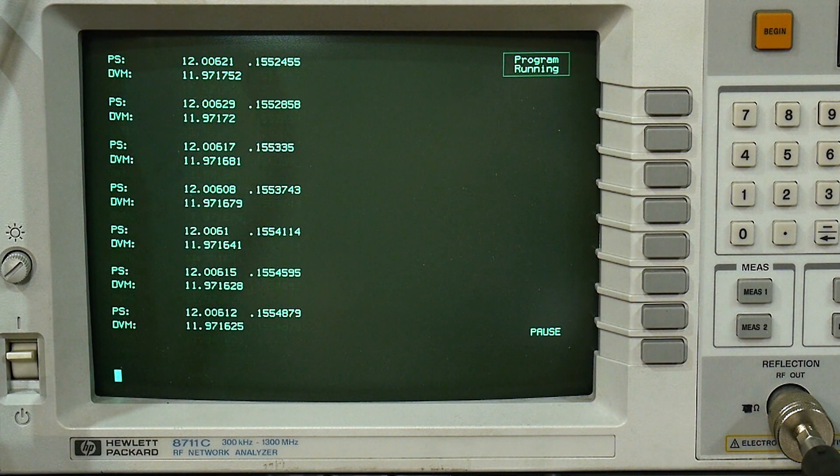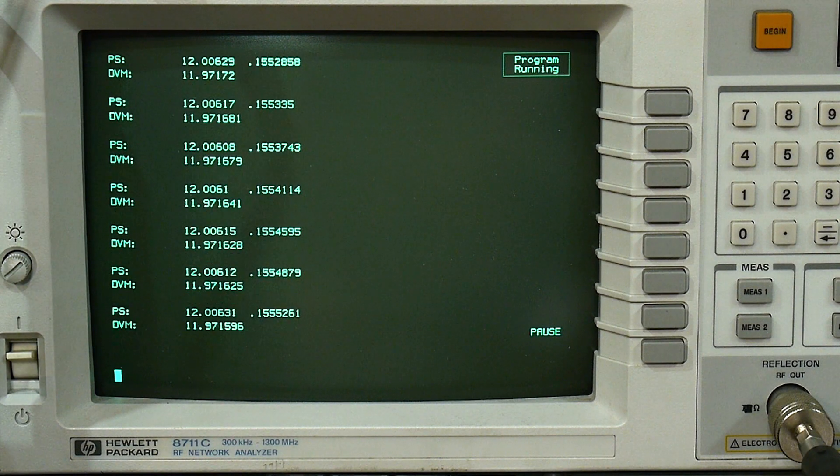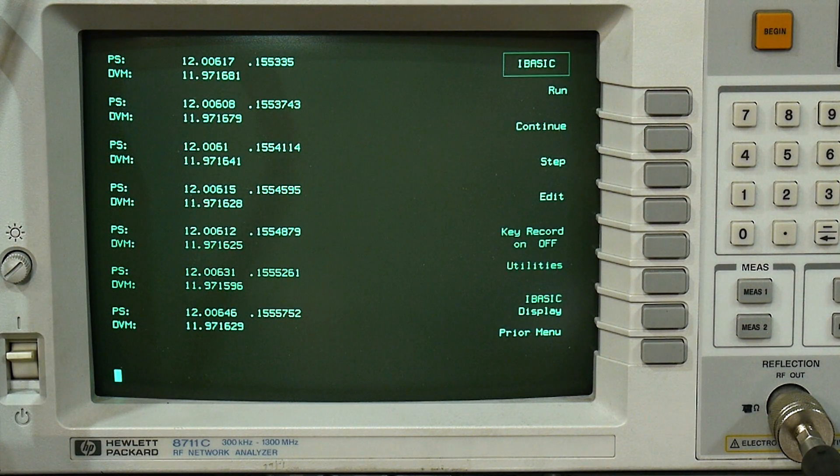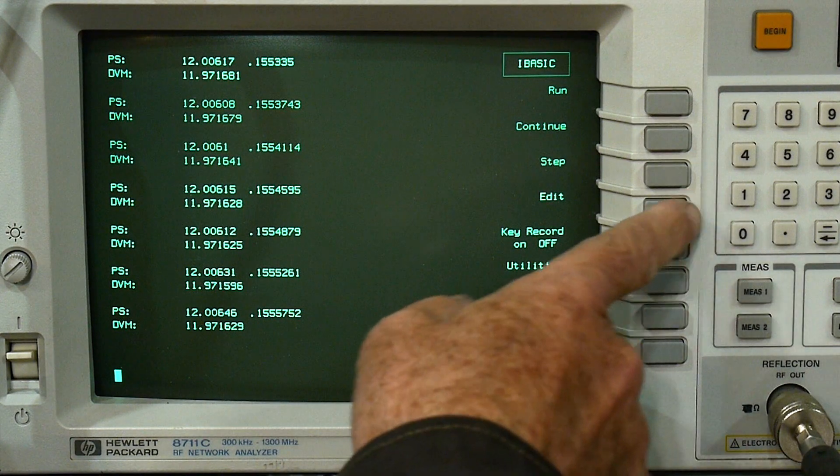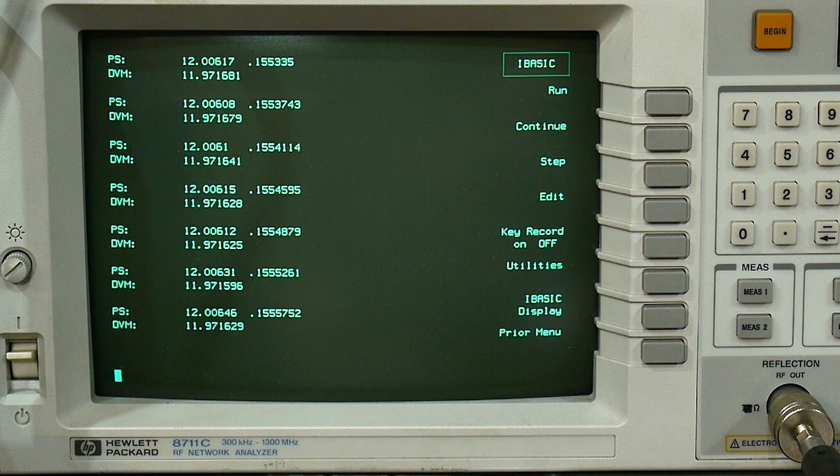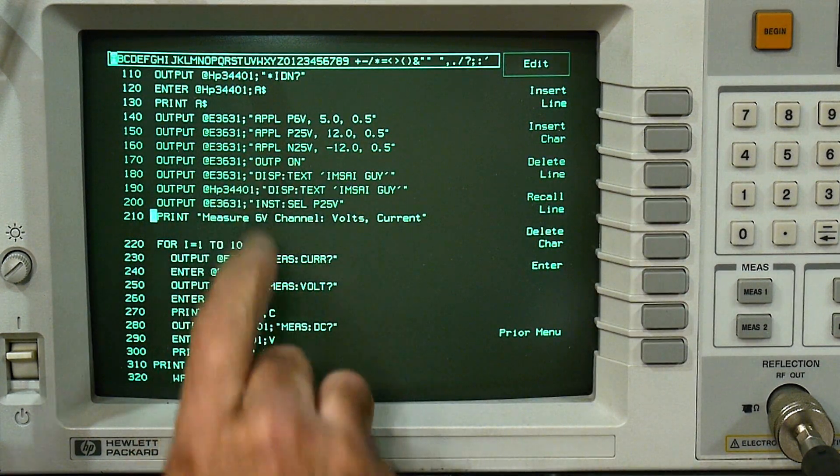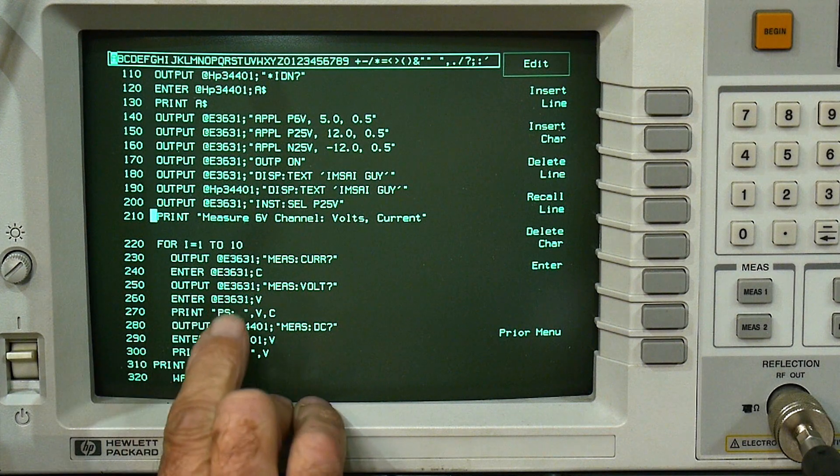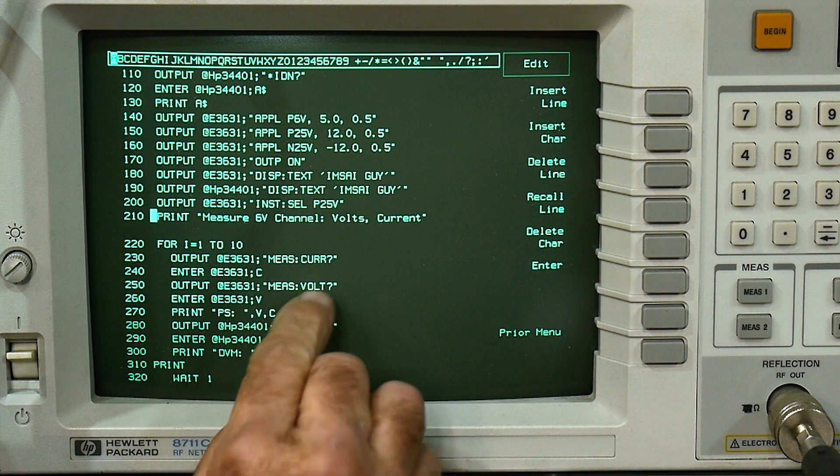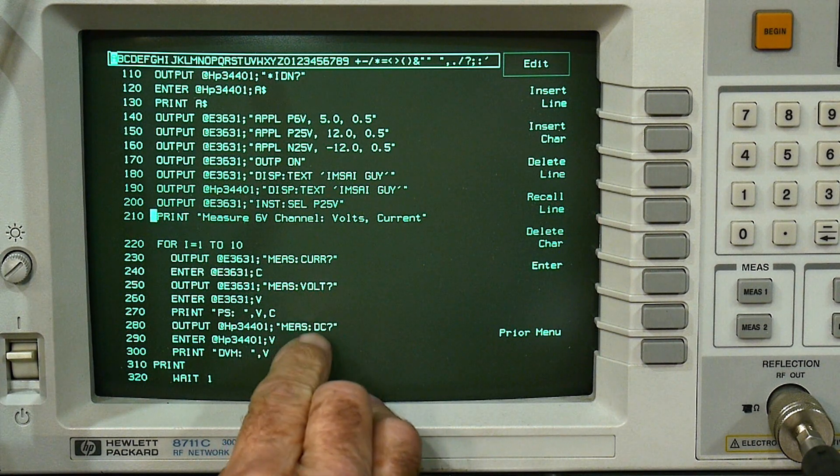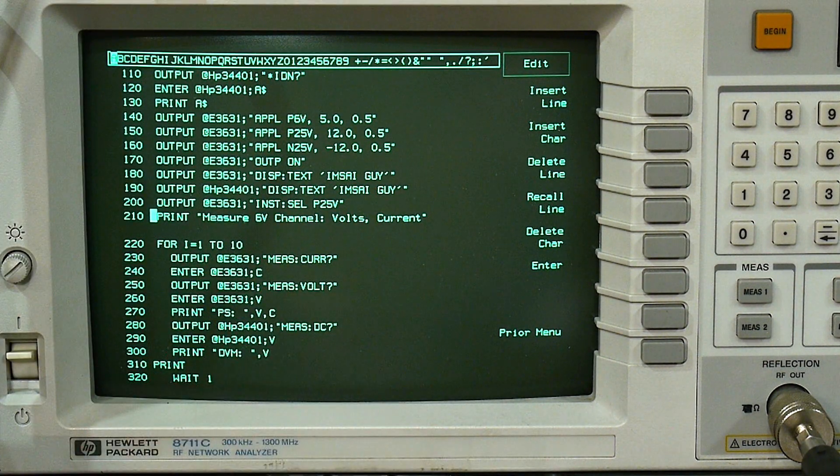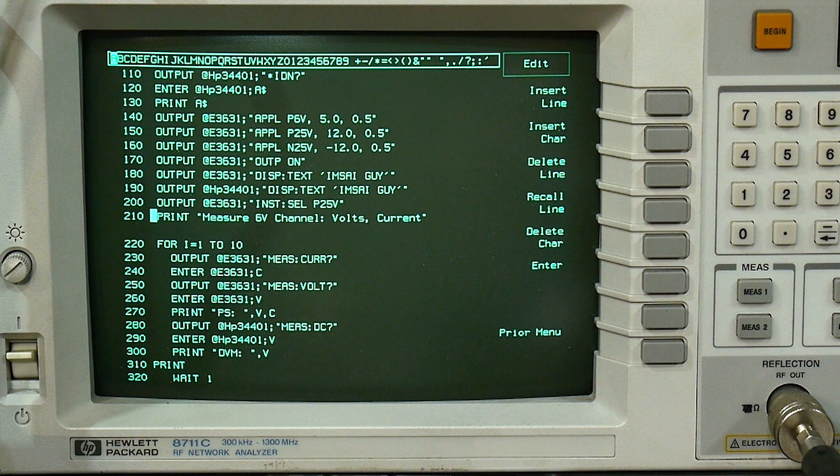I thought this was just a really quick introduction to HPIB programming in BASIC. It's going to look very, very similar if you do it in Python or in MATLAB or whatever. You're still going to give these same instructions. You're going to do an output and then you're going to give it an ASCII string, you know, measure volt question mark, measure DC question mark. It depends on the instrument. You need to read the manual.